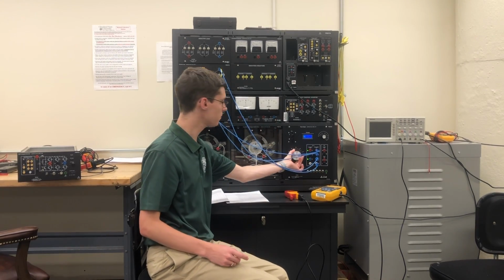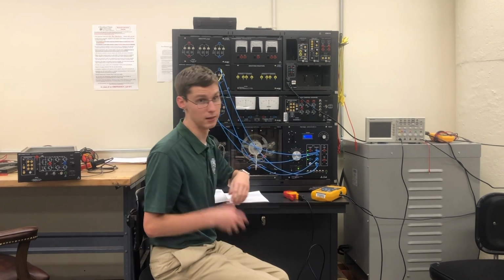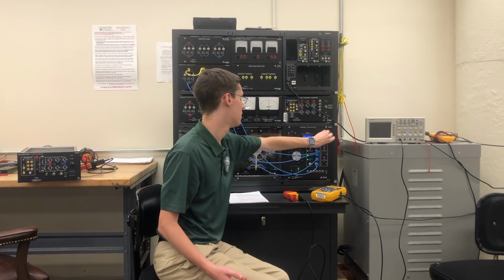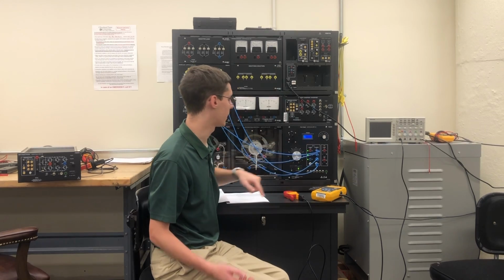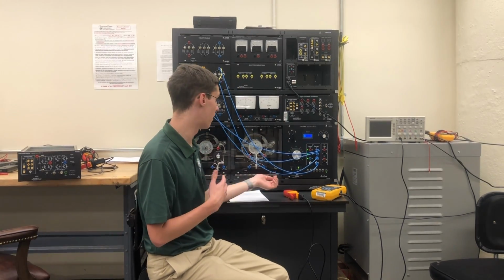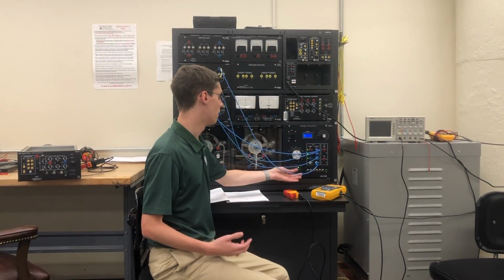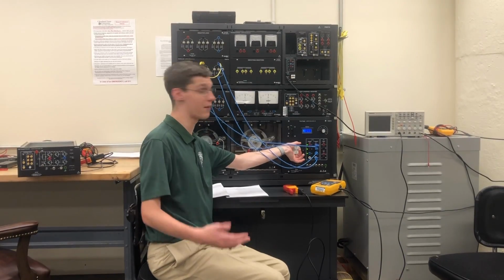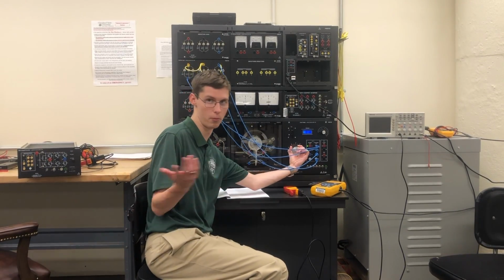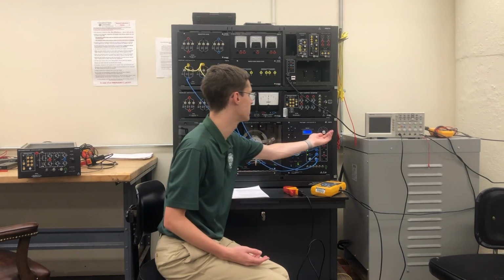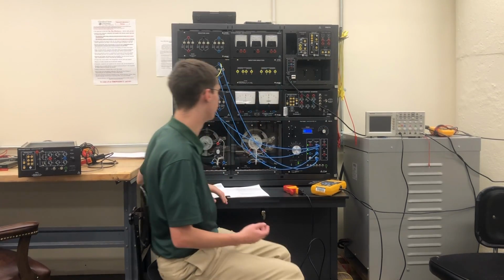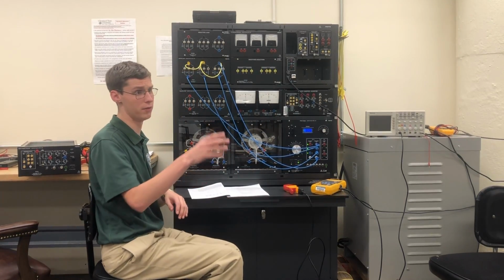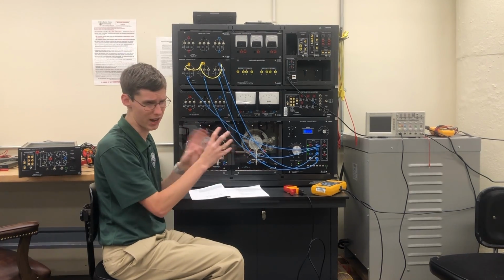and you'll watch as the voltage increases. If I want to measure the line-to-line voltage, I could turn it to 4 to 5, and I can measure the voltage between lines 4 and 5. These are 2 different measurements, so rather than having to calculate them like you would normally, this actually takes care of it for you. That's the same on all of them. All of them have the selector switch. They're just at different positions.